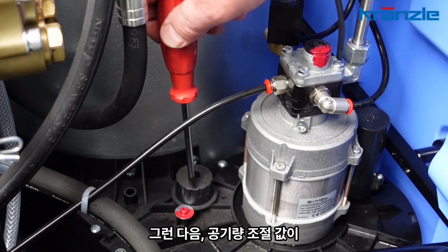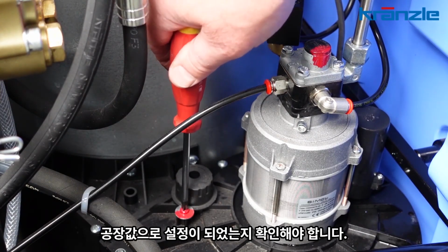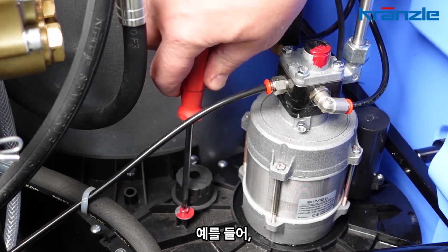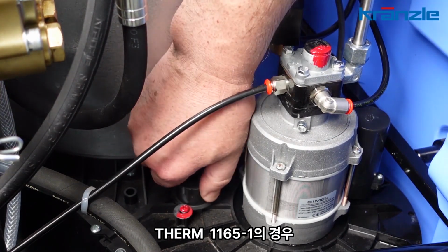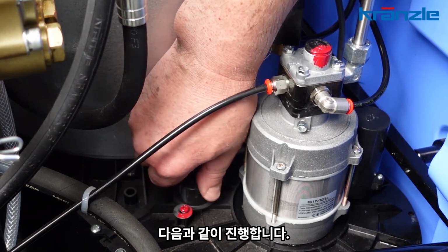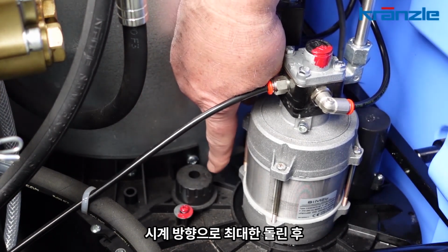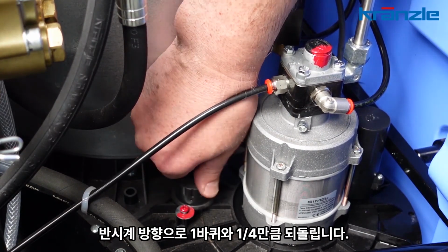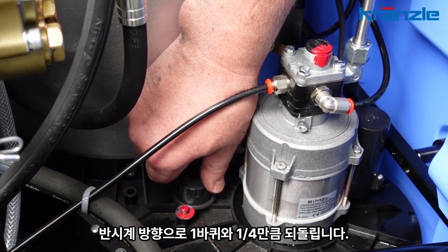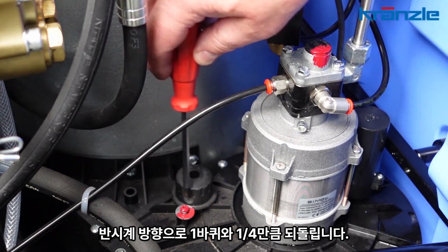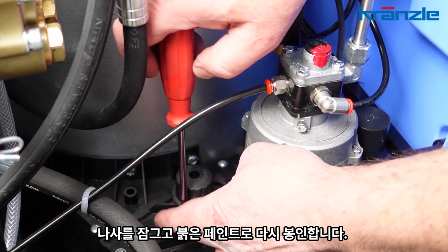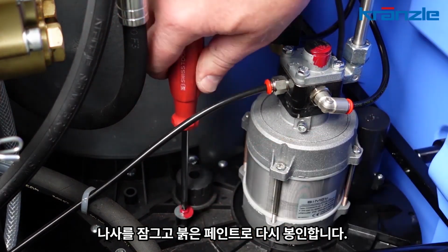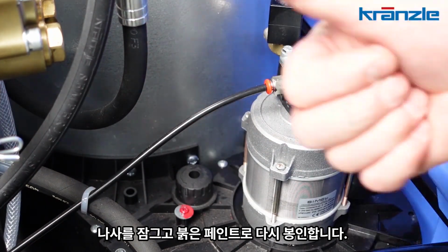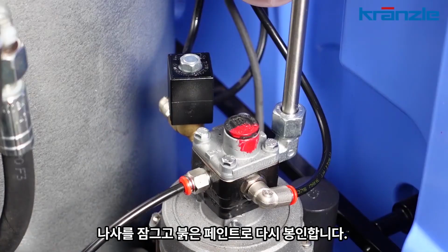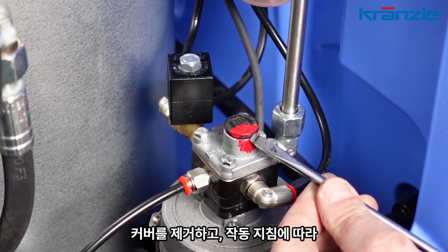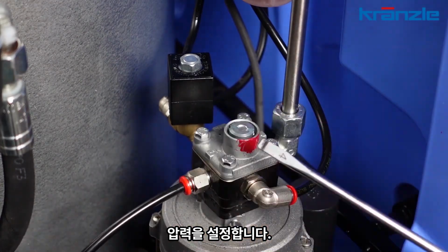If the factory setting of the air regulation has been adjusted, it must be checked. For example, for a Therm 1165-1, proceed as follows. Screw in clockwise as far as it will go, then turn back 1 1/4 turns counterclockwise. Screw the lock tight and seal it again with red paint. To adjust the fuel pressure, remove the cover and set the pressure according to the operating instructions.